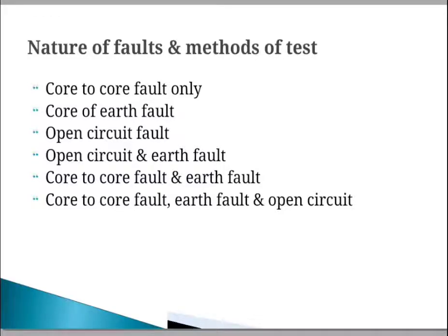Then what are the methods of testing? We have to use the fall of potential test. In that we have the Murray loop test, fall of potential test, capacity test, and induction method. If the cable is a metal sheathed cable, then we use the fall of potential test and induction method. These are the different methods we have to use to detect the different types of faults that occur in the cable.